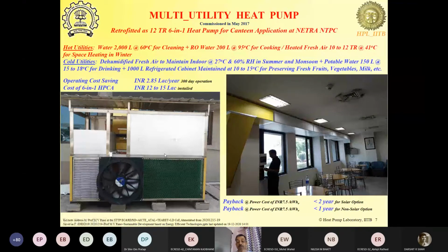Now, the heat pump operated only 6 to 7 hours a day, typically. Two hours during the morning breakfast period, 3 hours during the lunch period, and 1.5 during the evening tiffin period. But the chilled utility is available 24/7, not just on the days on which the institute is working. Even on weekends, there was enough storage to allow water to be supplied to the watchmen and the cleaning staff and the gardeners and all those who worked on the weekend also.